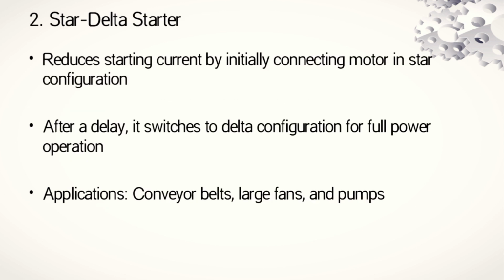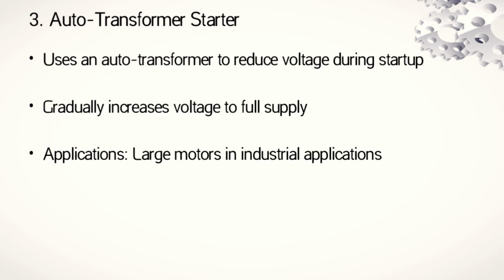The second method of motor starting is the star delta starter. The star delta starter reduces starting current by initially connecting the motor in star configuration. Star delta configurations are types of circuit connections that are talked about more in circuit network theory. After a delay, it switches to delta configuration for full power operation. Applications of the star delta starter are conveyor belts, large fans, and pumps.